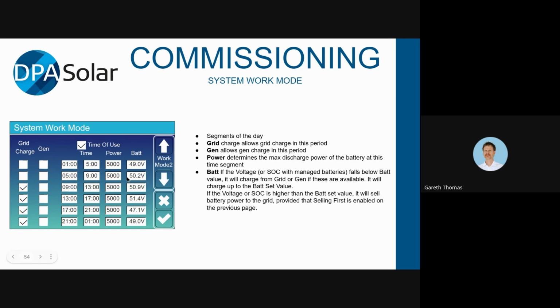When it might do that in quite a dramatic way is if that set point is quite different in the time period beforehand. So say between 5 and 9 it got down quite low, and then suddenly you kick over to this time period when grid charge is enabled, then suddenly it'll go, okay, grid charge is enabled, I'm going to charge up to 50.9. I might have been down to something much lower in that time period where there was no grid charge.